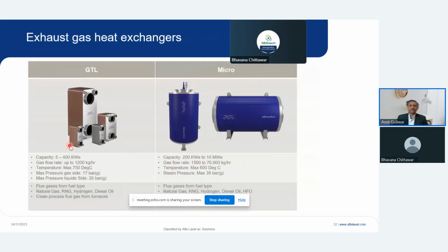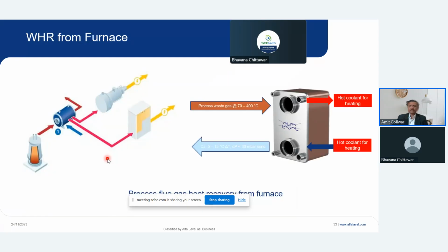And it's not necessary that the amount of waste exhaust gas should be high. There are heat exchangers made with capacity of just 5 kilowatt to even 400 kilowatt. So you need not go for very high capacity heat exchangers, and these heat exchangers are very compact, and can be designed to handle thermic fluid and coolants as well.